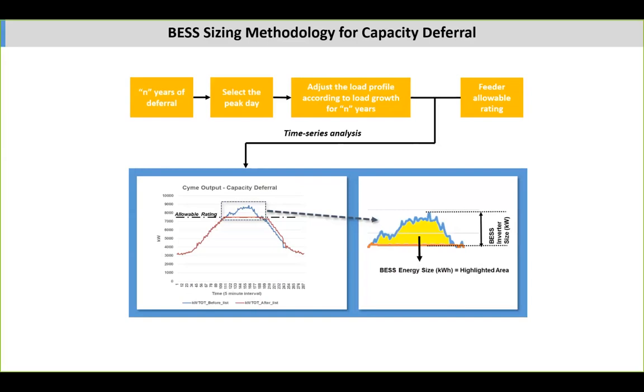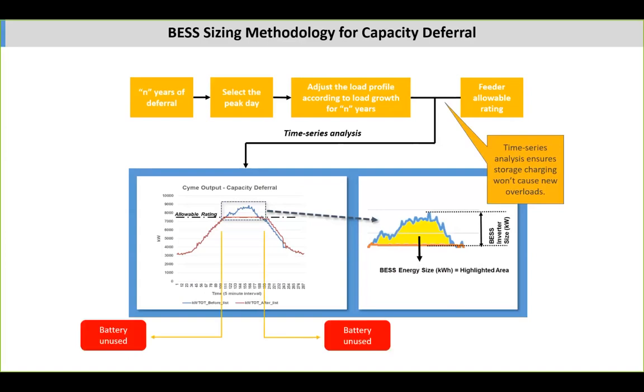There's a race here. The longer we defer, the greater the savings when we net present value back. But the longer we defer, the bigger the battery's got to be and the more it costs. So that analysis becomes a race between these two effects. To further complicate it, you can build the inverter and balance of plant for the forecast peak size at the end of the deferral period, and add battery capacity as you go along as needed.